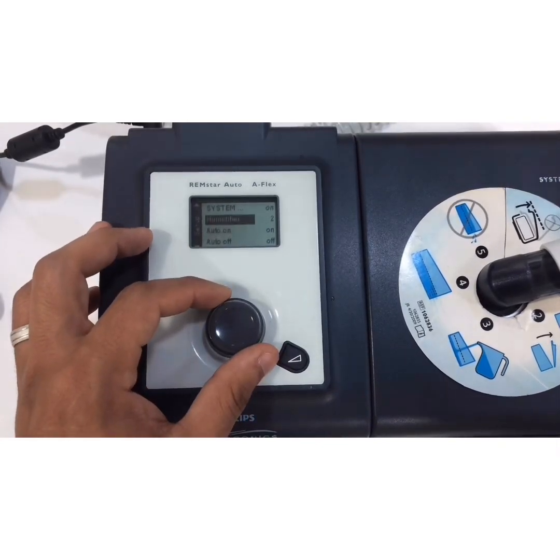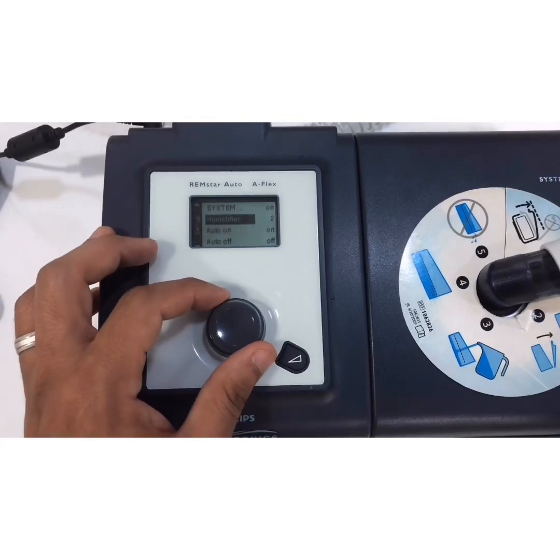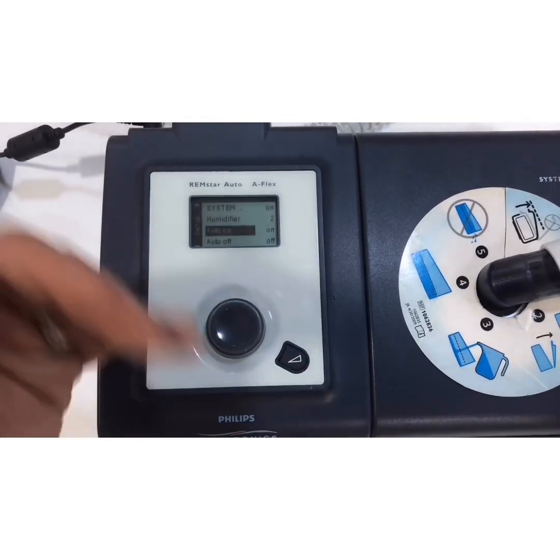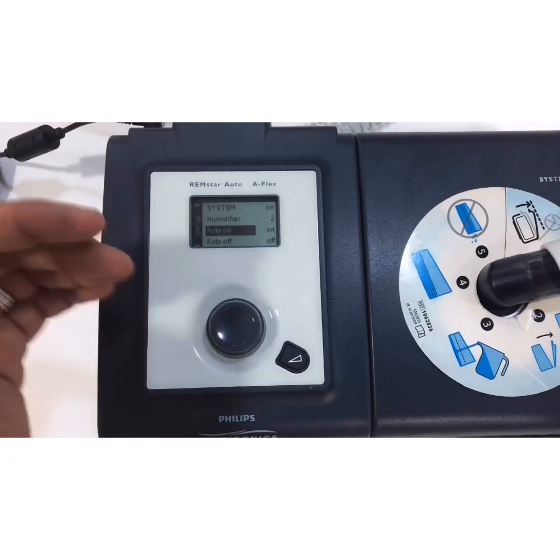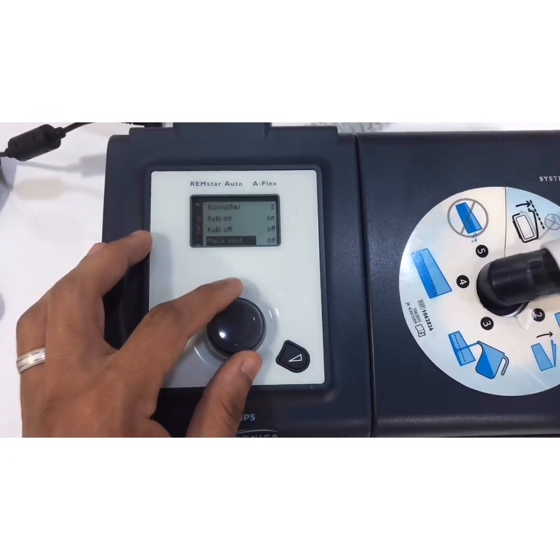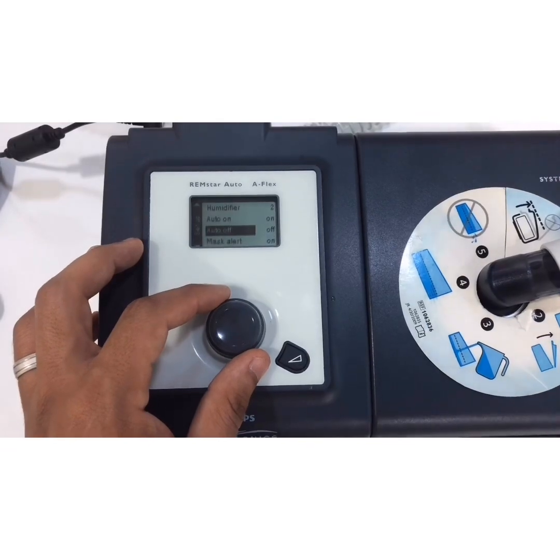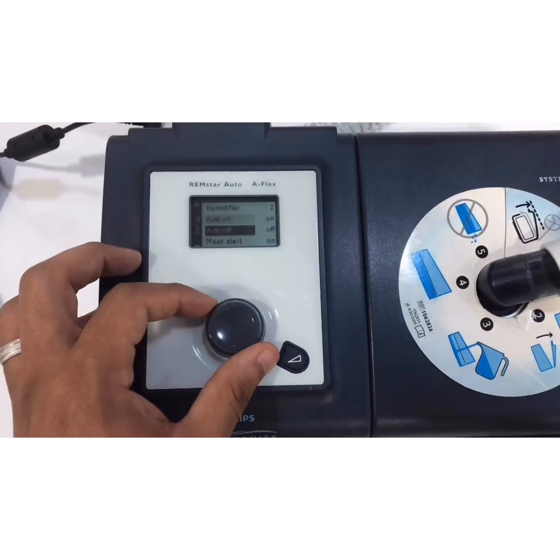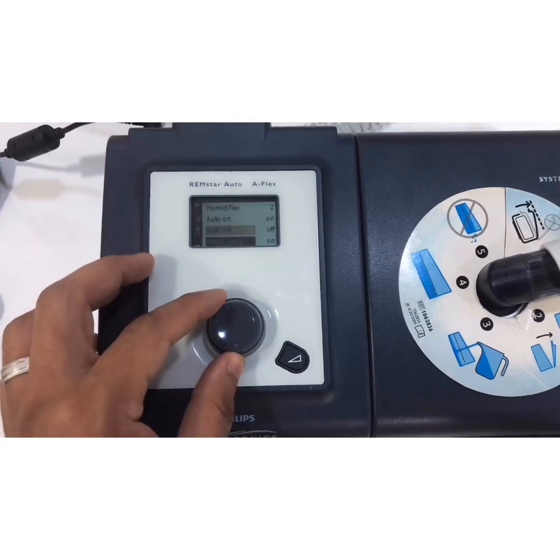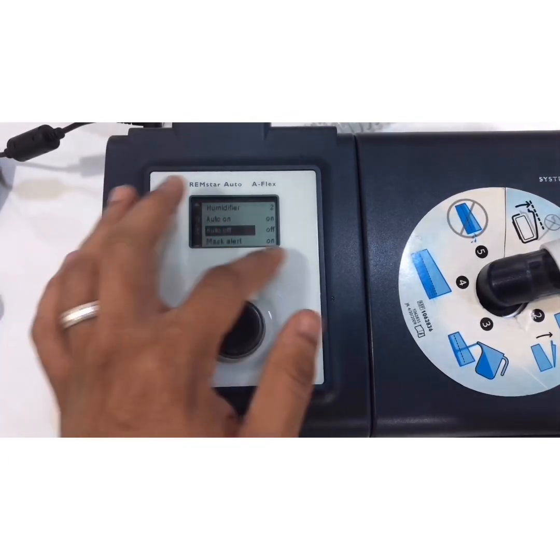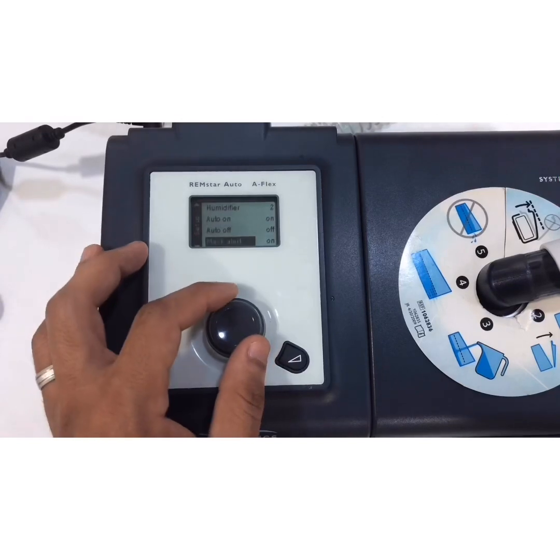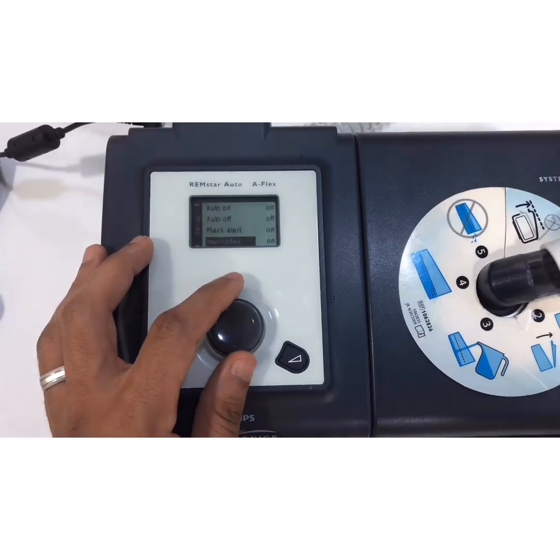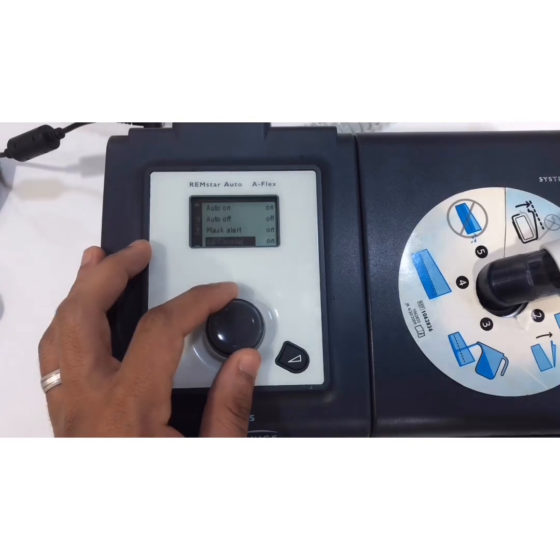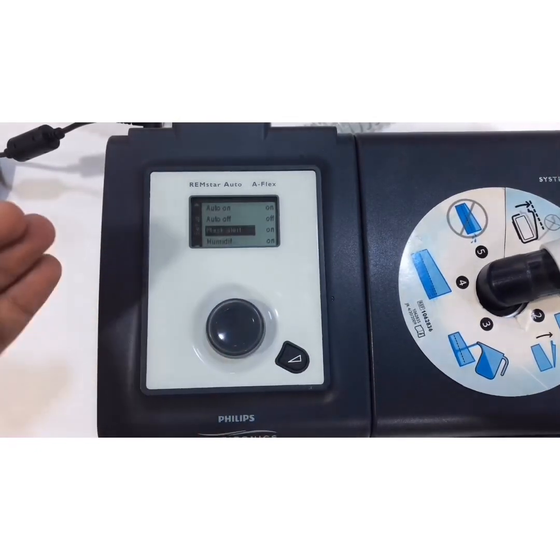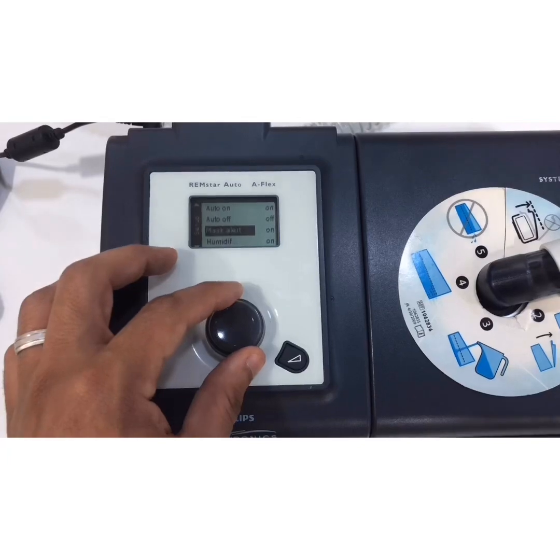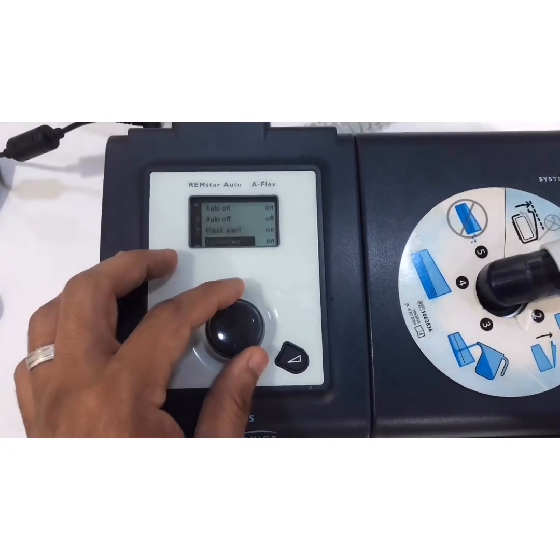Just ask the patient to put the mask on and breathe for a few seconds, and the machine will start working after a few seconds only. Auto off means once the patient removes the mask, the machine will stop working by itself. However, with this machine, the stop will be after almost two minutes, so for me, no need to activate it. Mask alert means in case there is intentional or unintentional disconnection of the mask or of the circuit, the machine will start alarming, which is a safety feature.